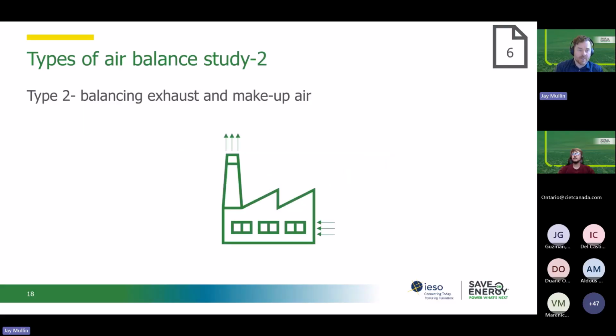The second type that we're focusing on today looks at that total supply, exhaust, and makeup air, and how that can be balanced to control the pressurization. So this solves for odors, fumes, dust moving between spaces, doors being difficult to open or close, pressure alarms, unstable system operation, and it looks more at things like total air supply versus total exhaust, makeup air availability, pathways, and the system response under real operating conditions. This is specifically meant to address those pressure problems, not diffuser problems. So those are two separate things to keep in mind in what you're looking for.